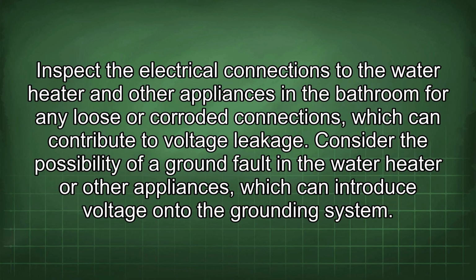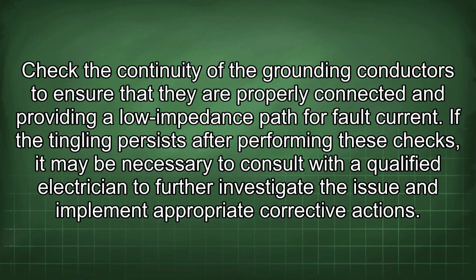Inspect the electrical connections to the water heater and other appliances in the bathroom for any loose or corroded connections which can contribute to voltage leakage. Consider the possibility of a ground fault in the water heater or other appliances, which can introduce voltage onto the grounding system. Check the continuity of the grounding conductors to ensure that they are properly connected and providing a low impedance path for fault current.